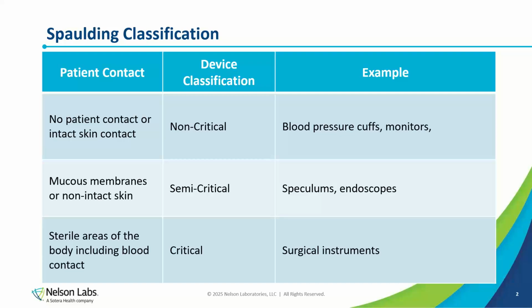And essentially, I would say it doesn't have a large impact on robotic devices, or on sterilization validations in general. You're still going to need to perform a sterility assurance level validation, and ensure that you can demonstrate proper lethality with your sterilization process using the appropriate BIs, placing those biological indicators in the appropriate locations. And then additionally, with any moist heat sterilization validation, you are going to need to perform a dry time validation as well. And then we also recommend doing temperature profiling of the chambers. But in terms of impact specifically to robotic devices, I can't think of any large impact.